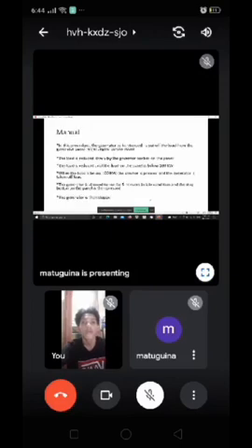Stopping can also be done in 3 methods: automatic, manual, emergency. Automatic: in this procedure, the generator is stopped by going into the PMS system in the computer and then pressing the stop button to stop the generator. Even if you try to stop the only running generator, it will not stop because of the inbuilt safety feature which helps in preventing a blackout condition.